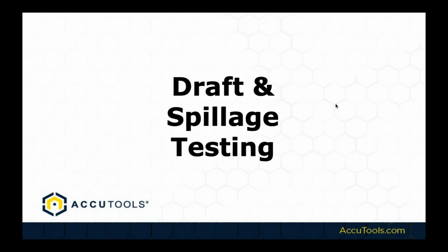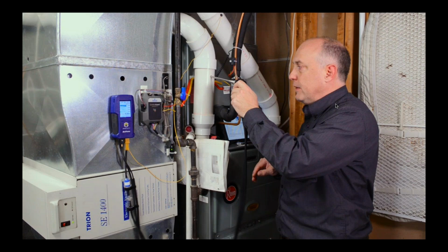So the next thing a combustion analyzer can be used for is draft testing and spillage testing. And here I am checking a furnace. I'm actually doing the draft setting on a 90 plus. Really what we're doing is just monitoring the pressure in the exhaust pipe to make sure that it's not excessive, indicating a blockage of the exhaust pipe. But you also have to have enough pressure that the flue gases can actually exit fully. Very, very important to look at the manual of the furnace and make sure that vent pipe was installed properly.